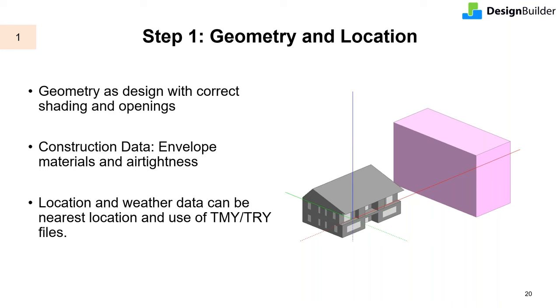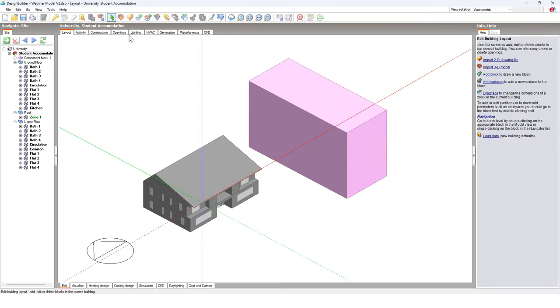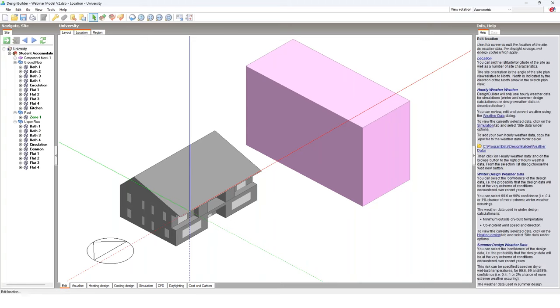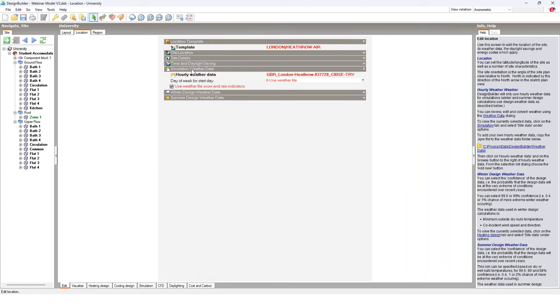Location forms the next aspect of the initial model setup, governing key factors including weather data and parameters for heating and cooling design calculations. An appropriate weather file specific to your building location should be used. For building-specific projections, if more accurate weather data is available from a nearer weather station in a climatically similar location, you should use that in baseline projections. It's important that the weather data used for baseline modeling should be typical years and not design years.